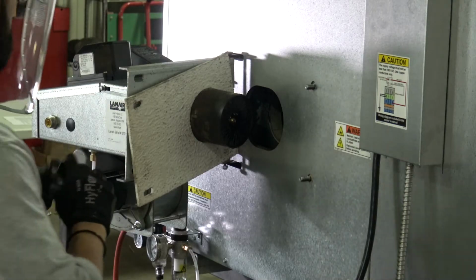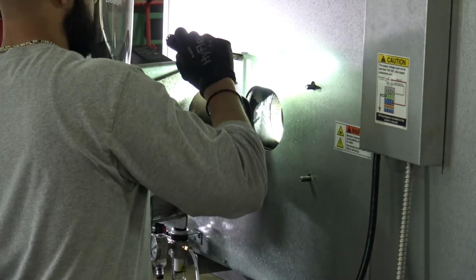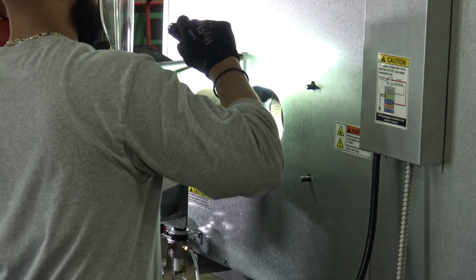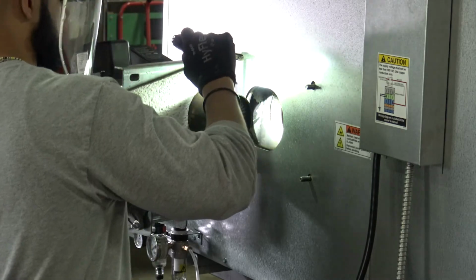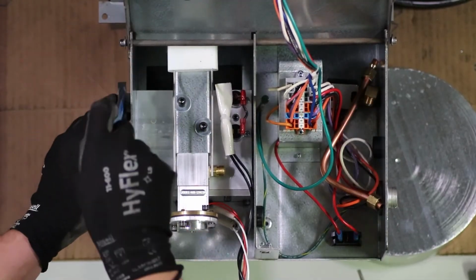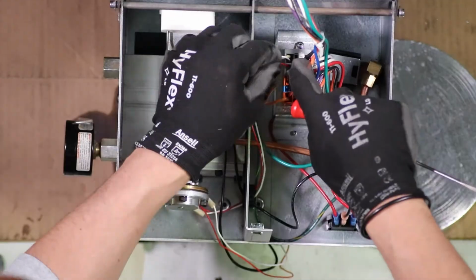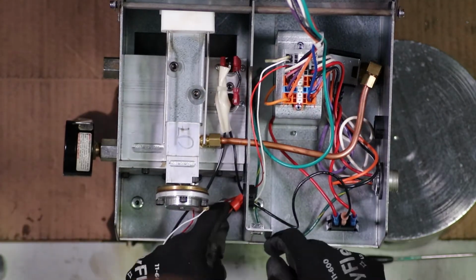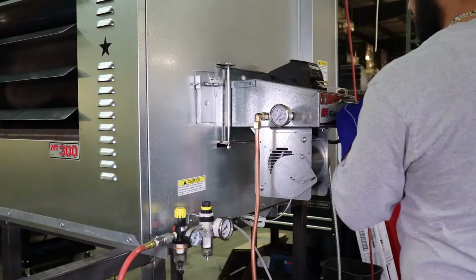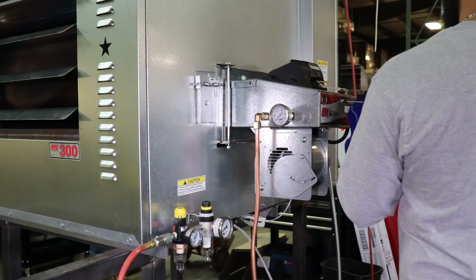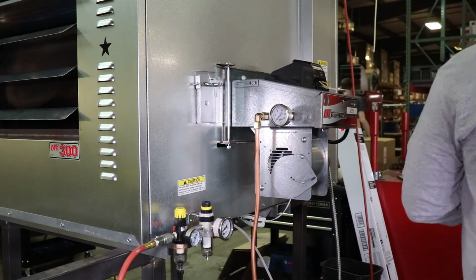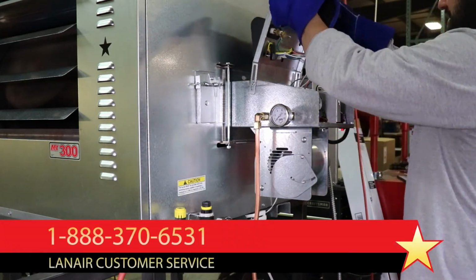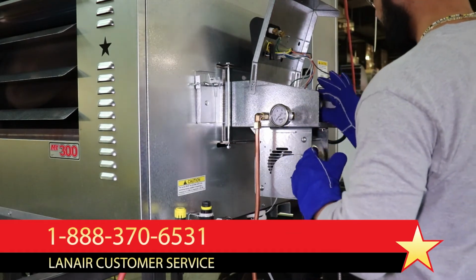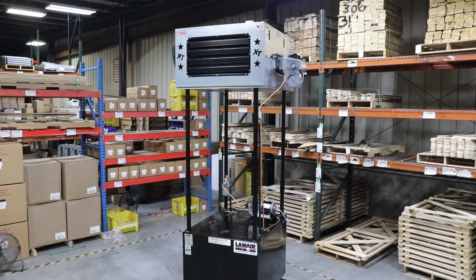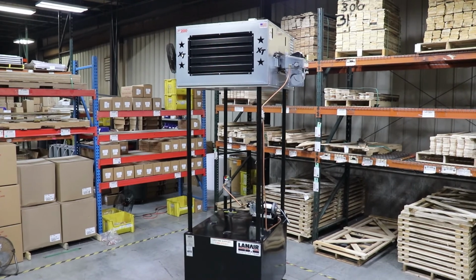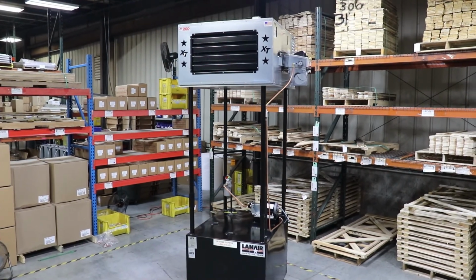Also check the position and gapping of the electrode tines. Refer to the product manual for specifications and adjust the electrodes if necessary. Continue by reinstalling the fittings, gauge, air line, and wiring to complete the installation of the replacement preheater assembly. Remount and connect the burner and reattempt the preheater clog test. If the issue persists, further troubleshooting is necessary. Contact Lanair technical support for assistance. If replacing the preheater assembly has resolved the issue, the heater is ready to return to operation.